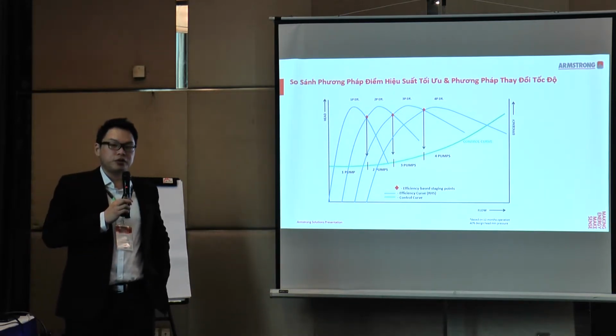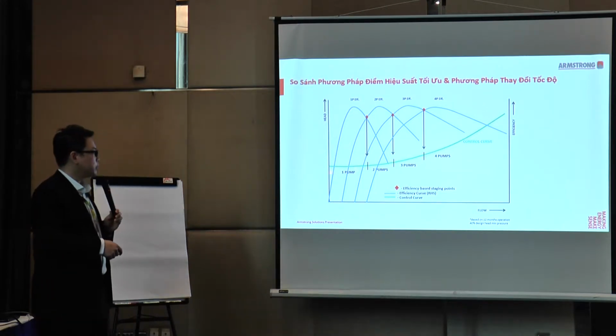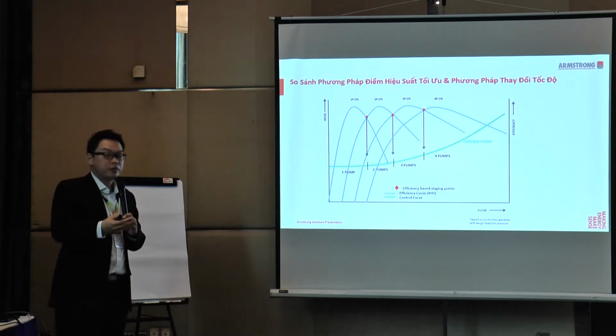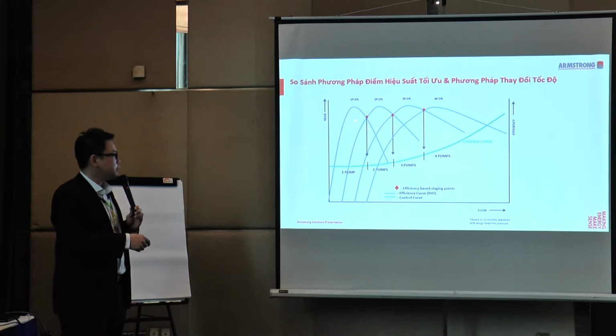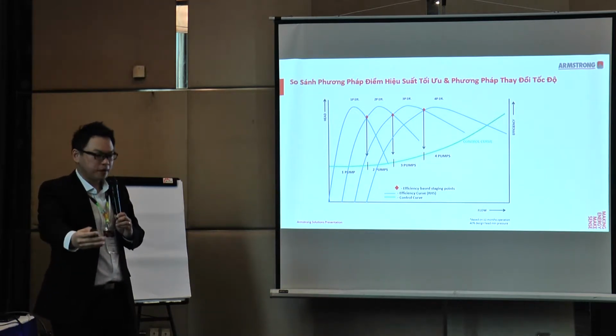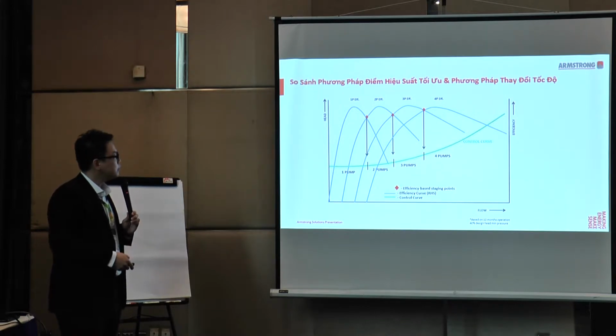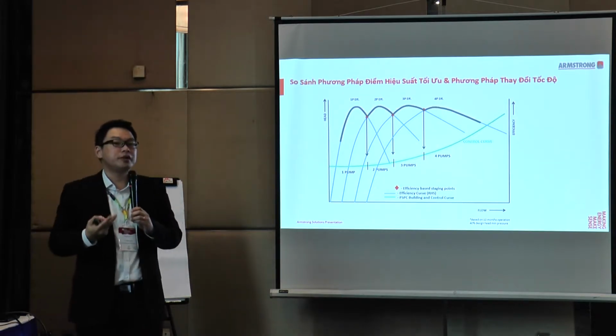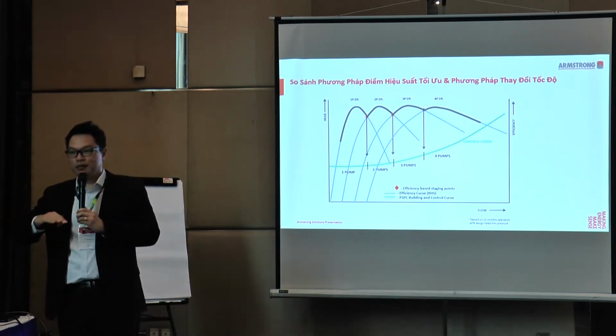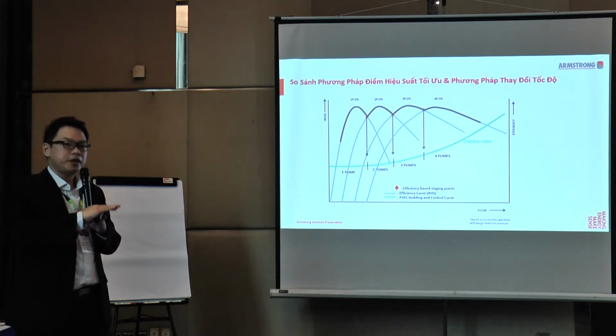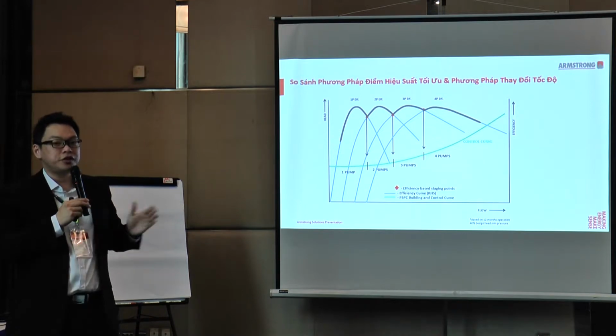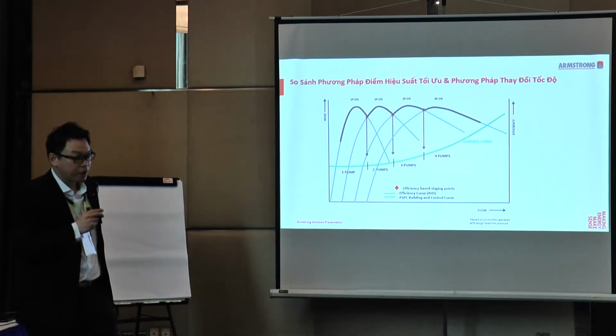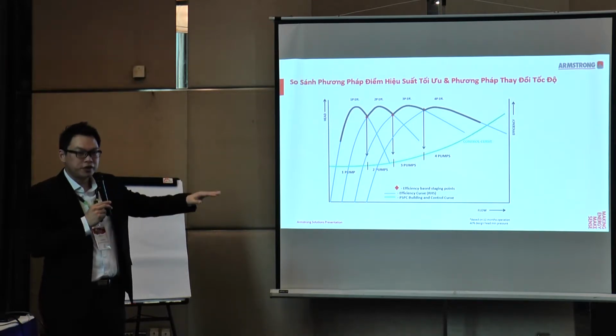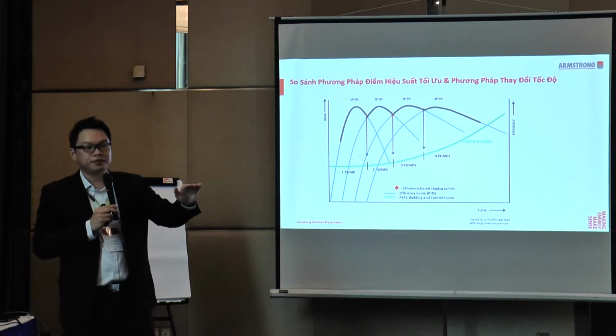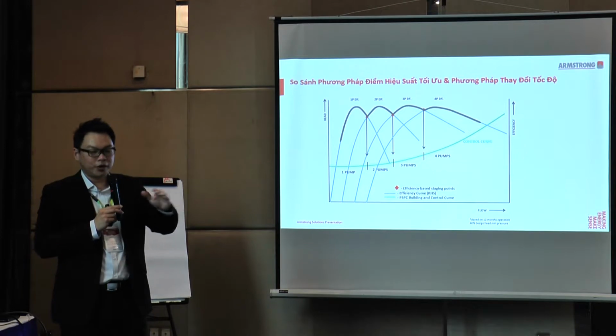This is another graph to further enhance your learning. Again we have our green control curve, and now we have 4 pumps in operation. The diamond points are the intersections between the first and second pump, second and third pump, and so on. So these diamond points are where the next pump is going to be turned on. Now we have a black line. These lines are the combination of the best efficiency points of all four pumps, to ensure that throughout the operation we are at the best efficiency level.